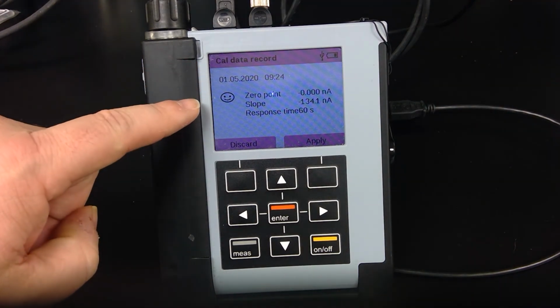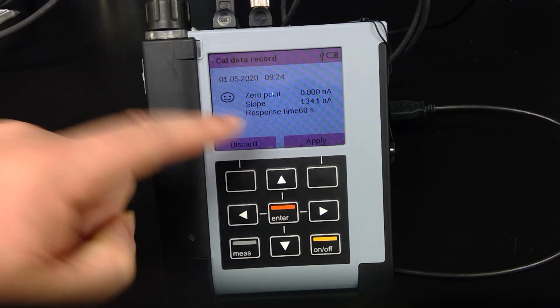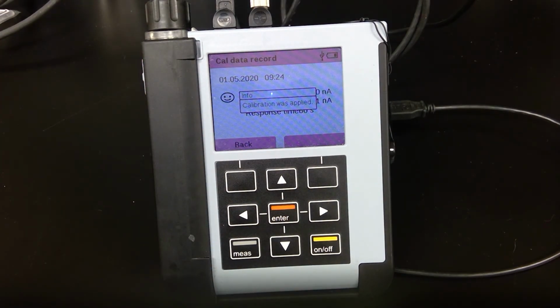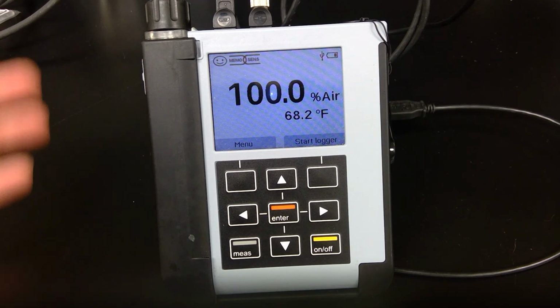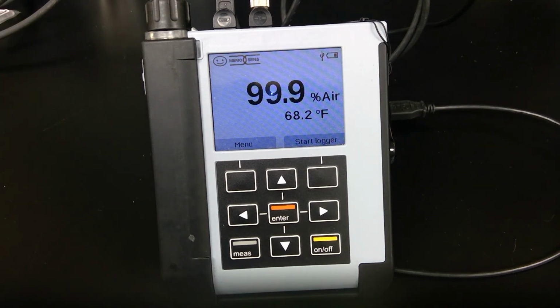So here are our calibration results: our zero point, slope, response time 60 seconds. I hit apply, and we're good. So at this point, everything is ready to go. This is ready to be taken into the field and swapped with a sensor that's already out there.